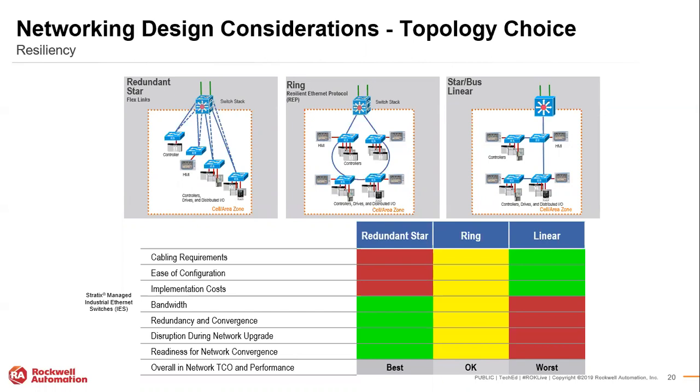And then everything underneath that, if this is a 5700, that could either be a star to the independent connections. So inside of a panel, you're doing a ring from switch to switch, but inside of the panel might be a star to the PanelView, to the ControlLogix, all those items. Or you might even do a ring inside of the panel and still do a big gigantic ring to the switches. So you can mix and match. But again, at this level, it's a little bit more complex, a little bit more cabling that you have to run. And the big piece you have to worry about on this side is if you're putting something new in, you have to be conscious of where the cabling is going and where power is going.